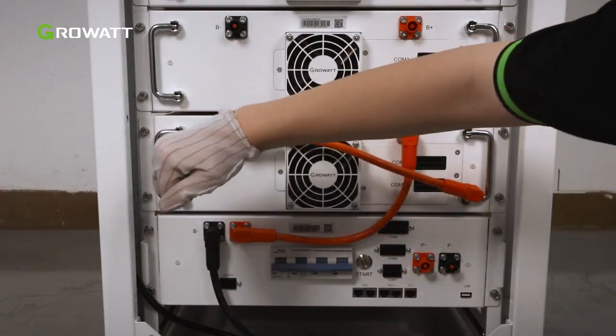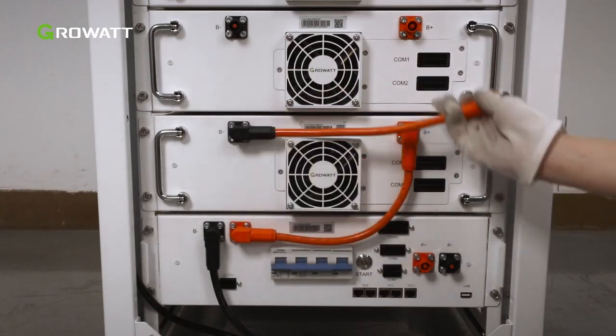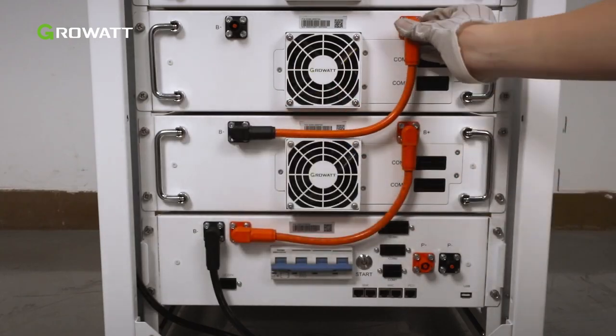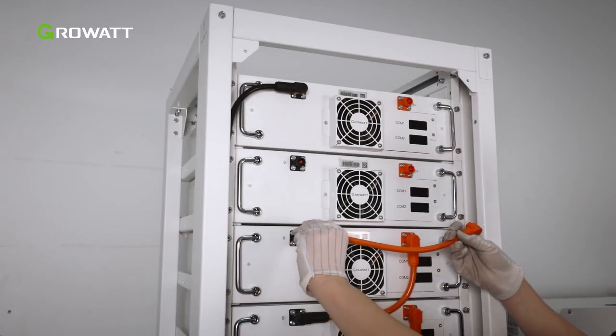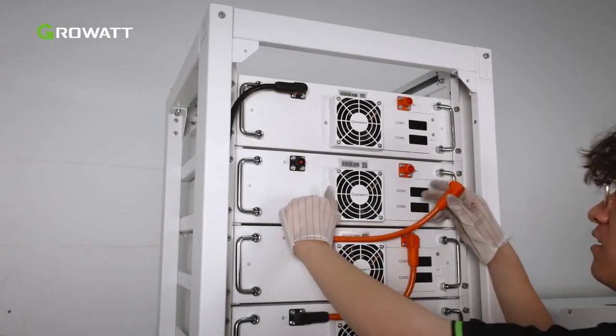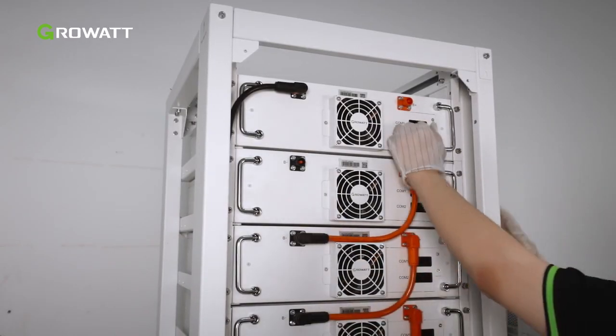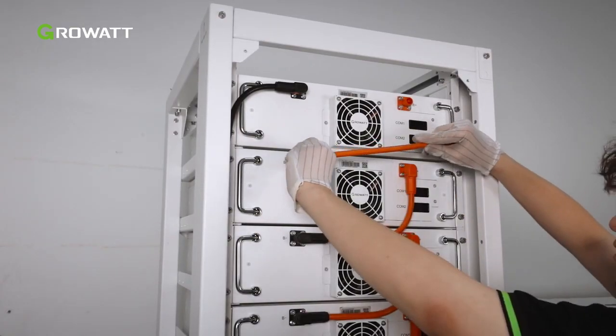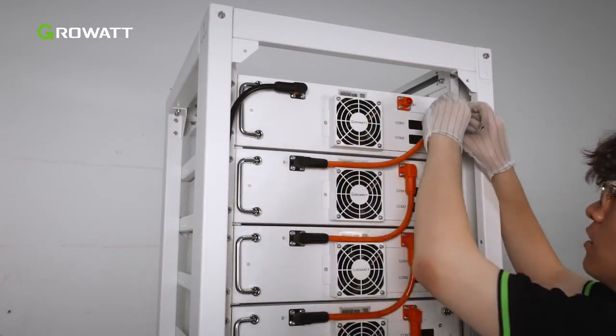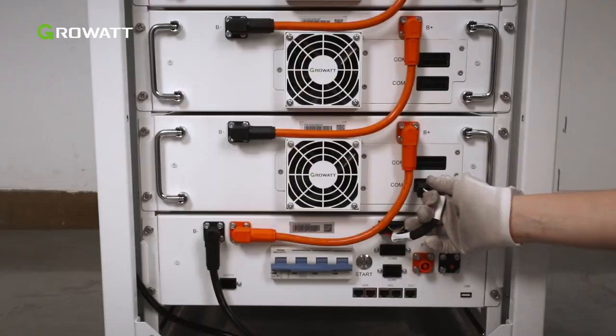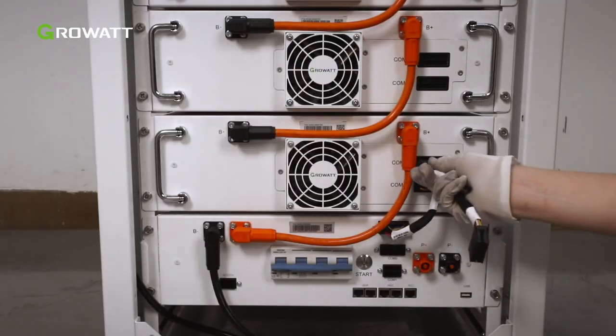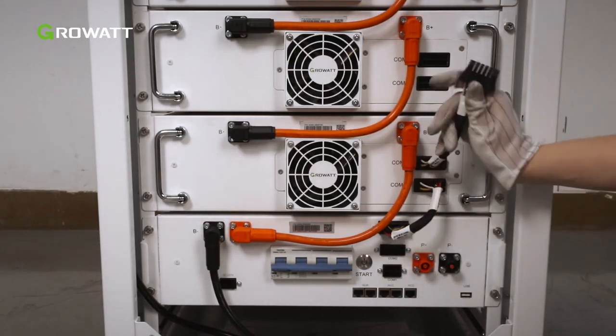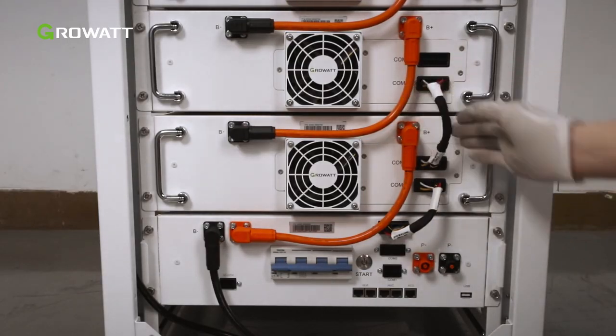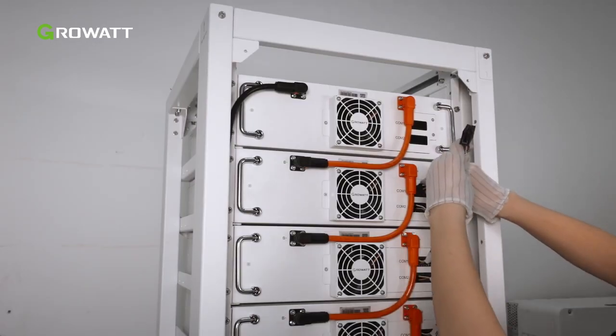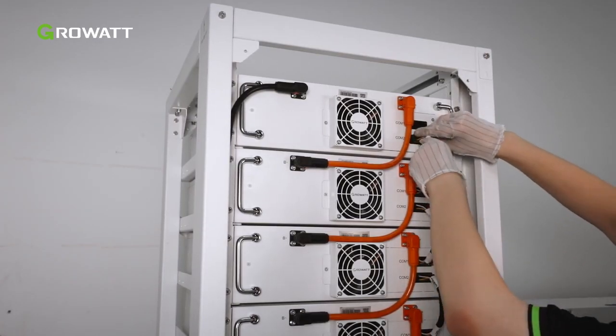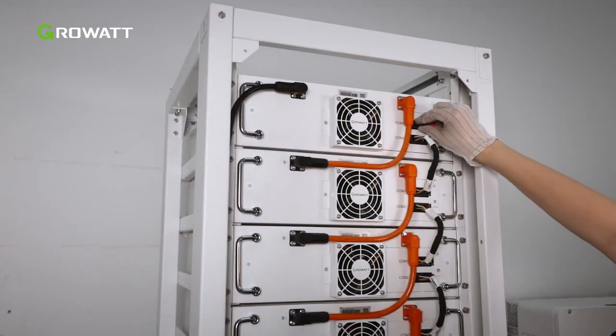Then connect the series power cables and communication cables between the batteries as shown. When connecting the terminals, ensure that you hear a click sound. Please gently pull back the cables to ensure a secure connection. And install the signal shorting cap.